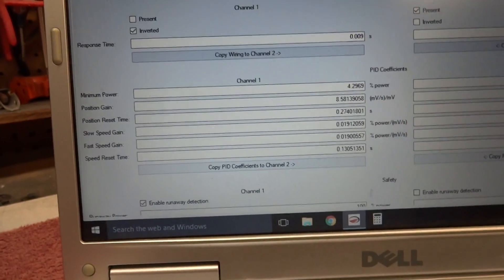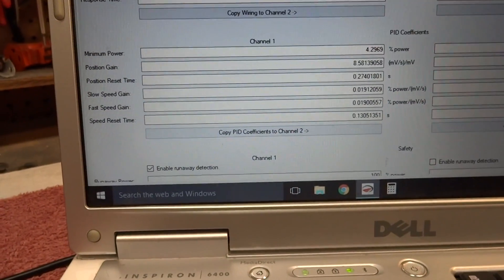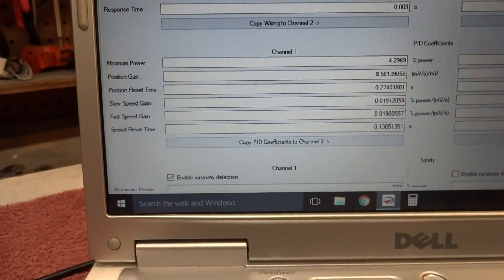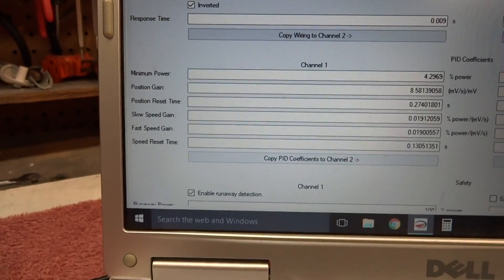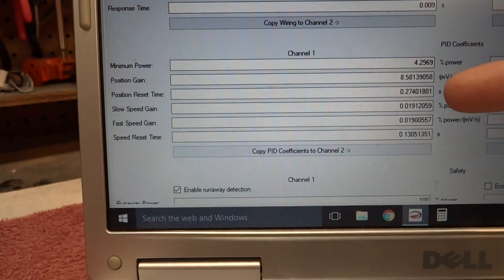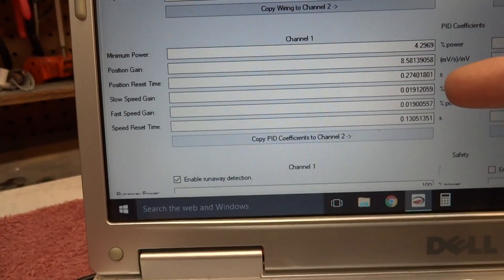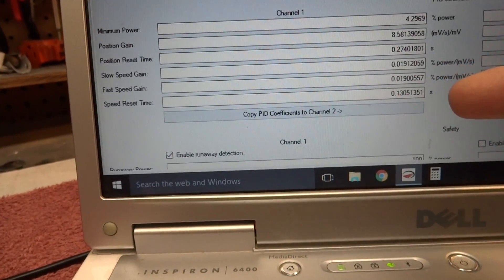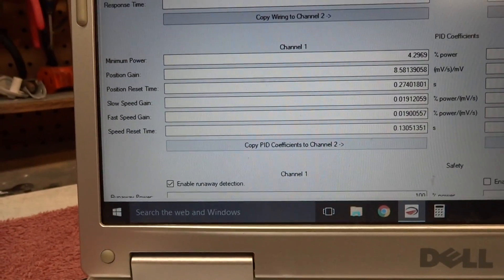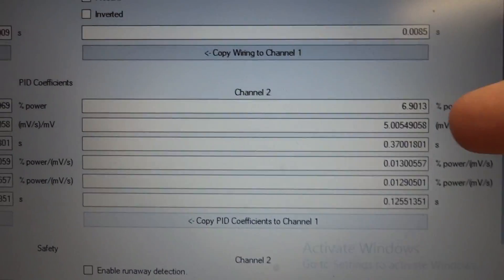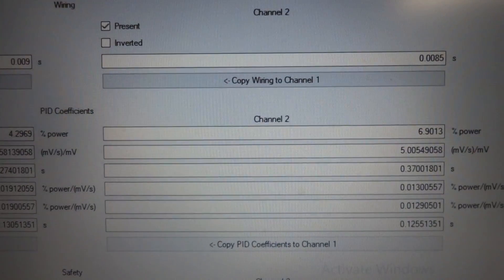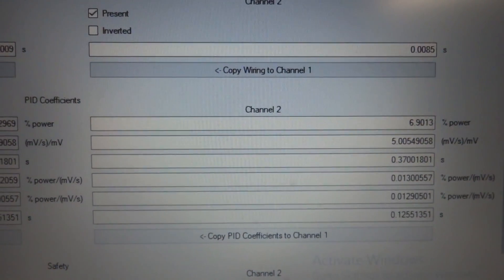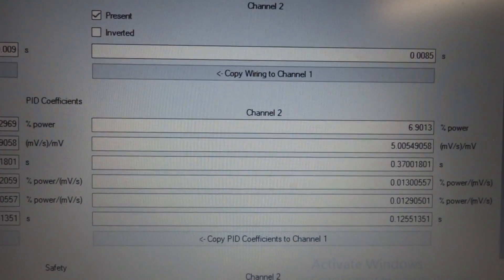This is the section down here, is your PID coefficient settings. And usually you have three settings for PID. This has one, two, three, four, five, six. It has a minimum power setting, and they tell me that's to overcome resistance when the motor starts up. It has a position gain setting, a position reset time, slow speed gain, fast speed gain, and speed reset time. So there's six settings I had to tinker with on this side. You can see all the math equations here, and most of my settings were done right here. And like I said, it took me like two weeks to get everything going. It was frustrating, I've got to admit, it was frustrating.